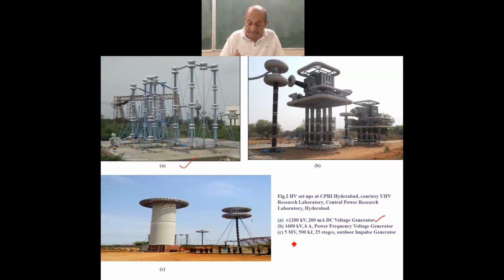C, as you can read it here, 5 MV, 500 kilojoule, 25 stages. That means each stage is generating 200 kV, an outdoor impulse generator, which is housed inside here. To protect it from the adverse weather conditions, it has been housed in a closed chamber, you can say. And this is the high voltage electrode on the top, segmented disc electrodes. In here also, segmented disc electrodes are being used as high voltage electrode. On the left is the actual impulse generator, 25 stages housed inside the tall enclosed chamber.